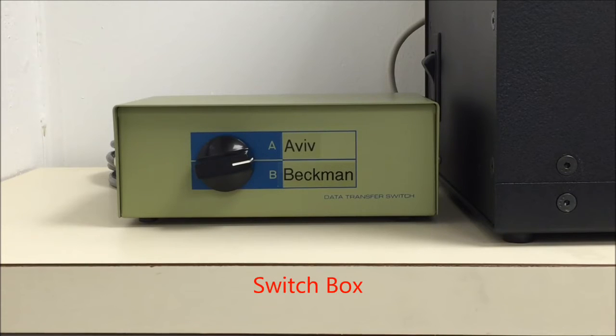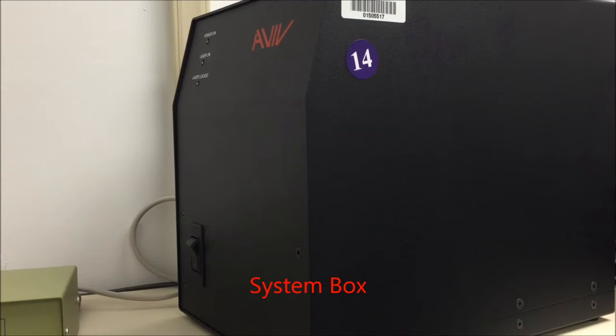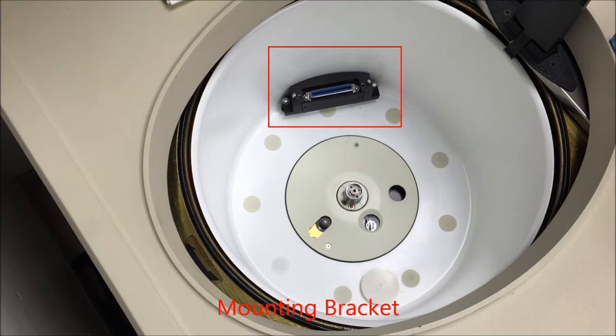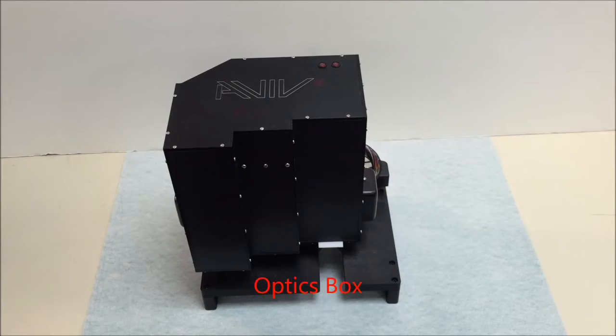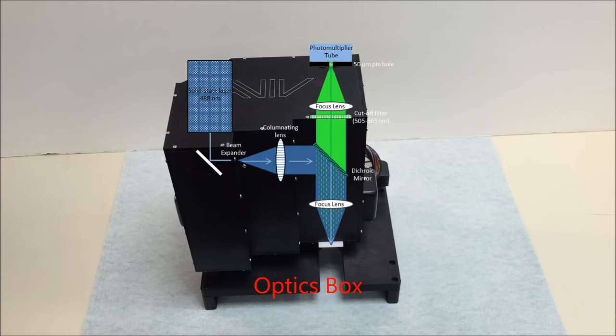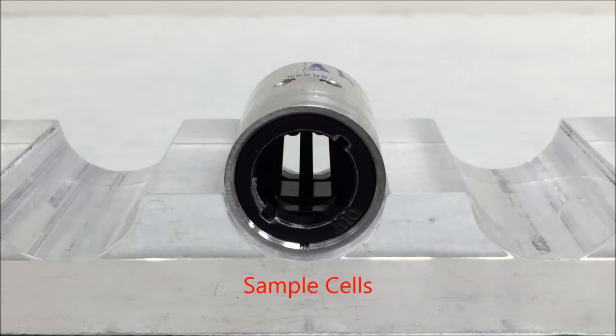The Aviv fluorescence detection system includes a switch box at A position, a system box, a mounting bracket, and an optics box. The optics box contains the light source, detector, and optics. In this demonstration, we use double sector centerpieces for cells, comparing with other detection systems. The fluorescence detection system directly acquires specific fluorescence signal from samples, which doesn't need a reference sector.